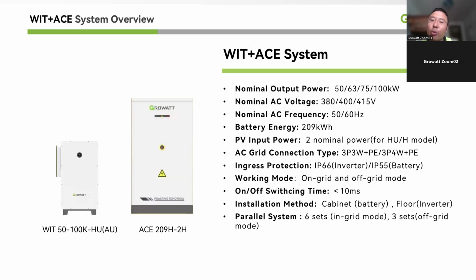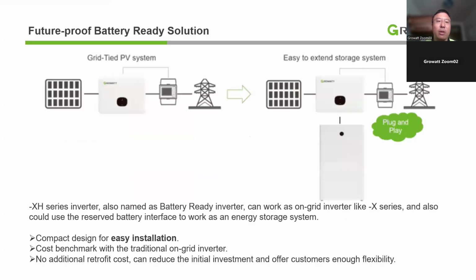The battery, we only have one size, so obviously the battery size is only 209 kilowatt hour. The inverter can be paralleled together in on-grid mode, up to 6 of them, giving you 600 kilowatt load capacity. In off-grid mode, it can take 3 paralleled together to give you 300 kilowatt off-grid load capacity.